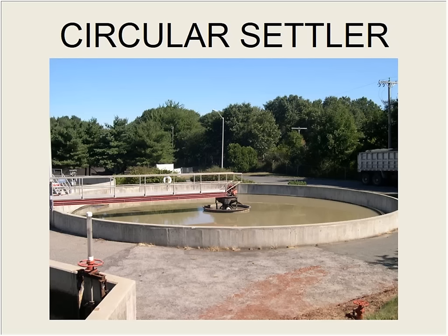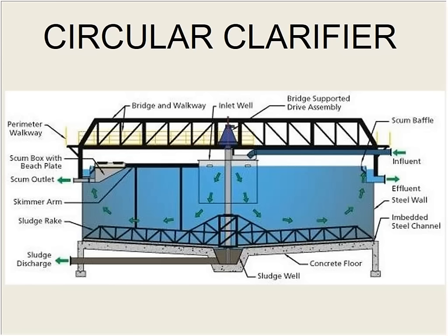Can also be done with a circular settler. Rectangulars are much more common on the primary end because of economy of construction. You've got common walls, and civil engineers build these places, and that's what they like. I haven't picked out a civil engineer yet, have I? Circular clarifiers, same thing. The water's going to flow into a well here in the center. It's going to slowly work its way to an overflow weir on the outer circumference of the tank.